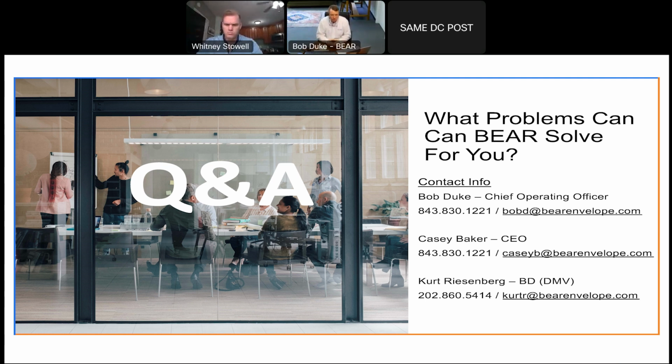So it's a good question. And yes, if your building is running pretty ardently in a negative way, when you open up that door, you hear the whoosh. And as a quick sidebar, 85% of all buildings typically run negative. Yes, put a pipe out for makeup air, stub it into the back of your air handler, and that can turn that situation around. Excellent.